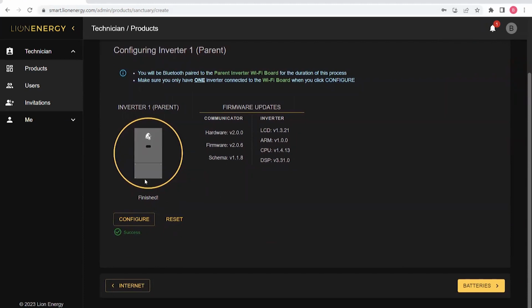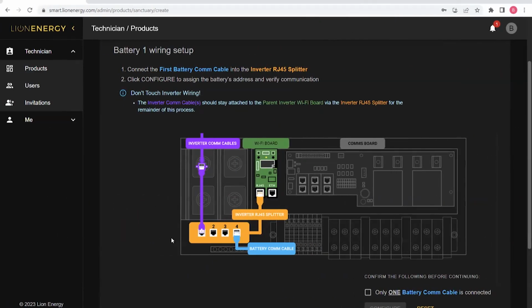Seeing that my inverter has been configured successfully, I can move on to the batteries. We have an image showing the process for configuring them. Our inverter COM cable is connected to our splitter, which connects to the inverter COM port on the WCM. I need to take one of the batteries and plug it into the splitter. This process serializes each battery so the system can identify which is which.